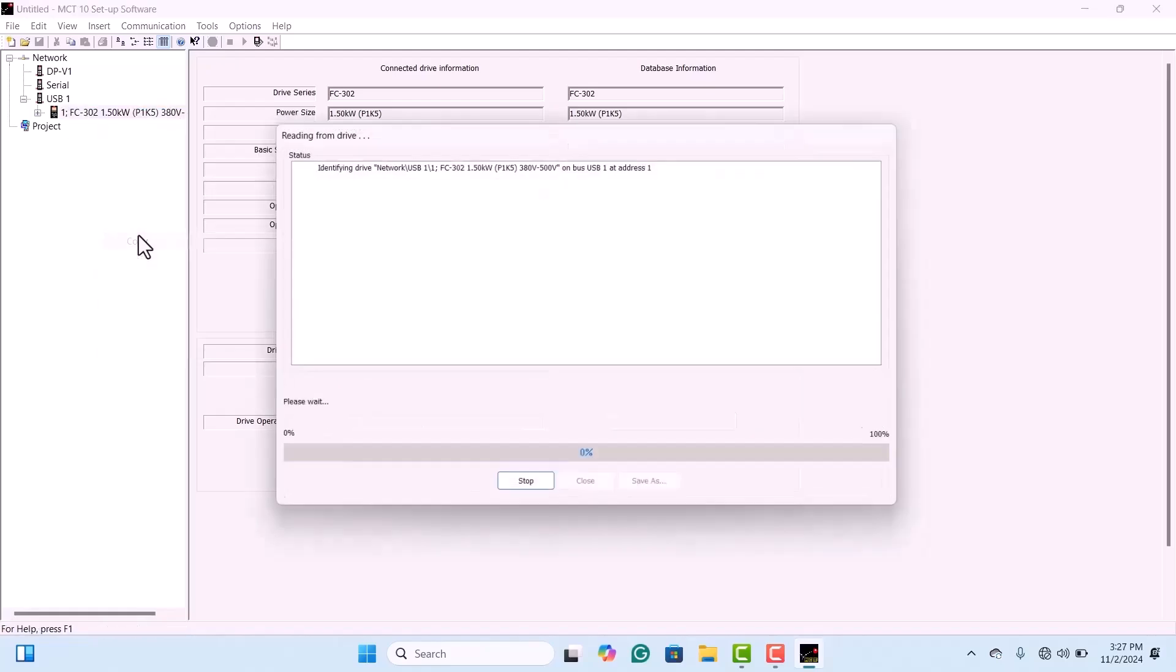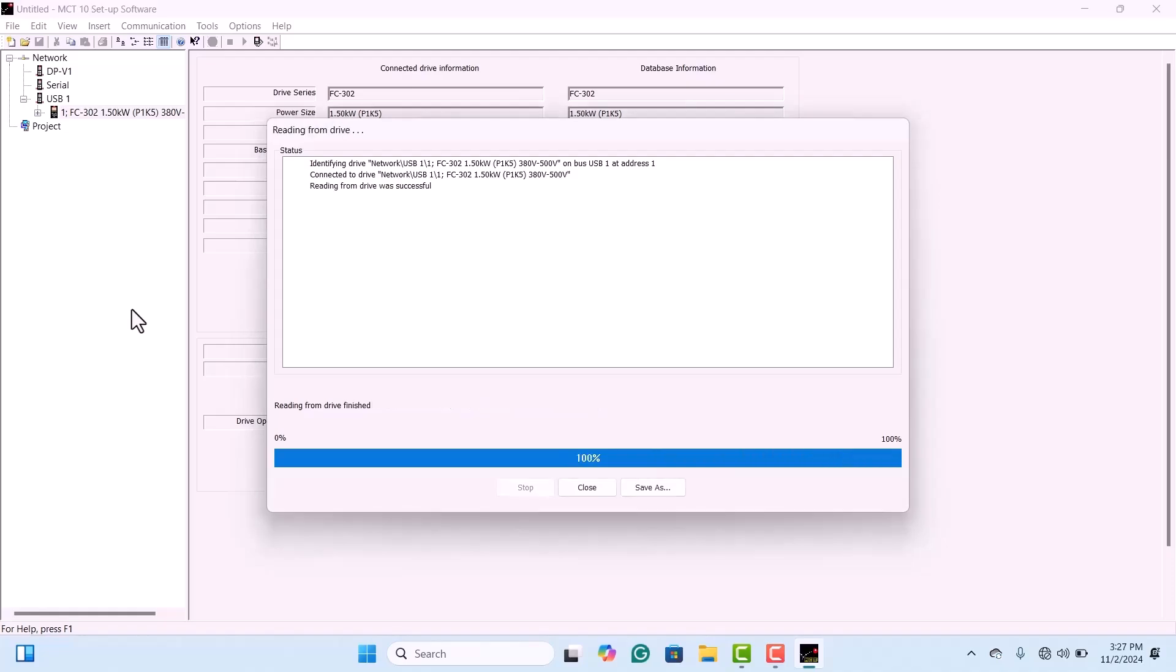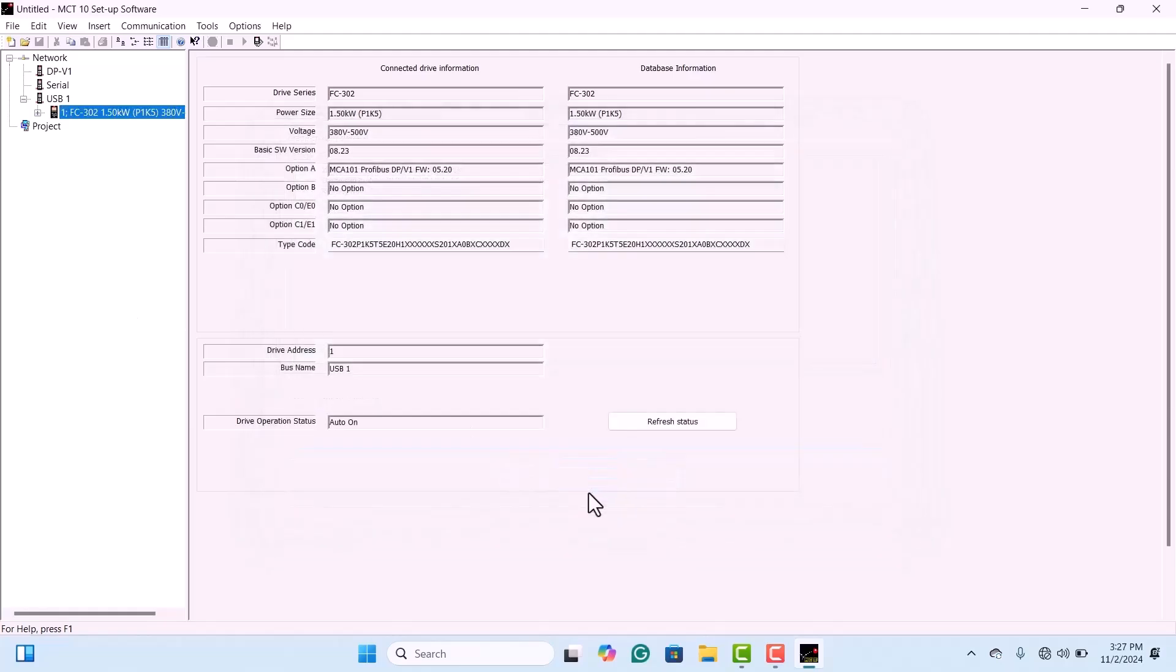To download the parameters, click on the Copy option. This will read the parameters from the drive, allowing you to paste them in the project section as a backup. Note that using the Read data from the drive option alone won't let you paste the parameters into the project.